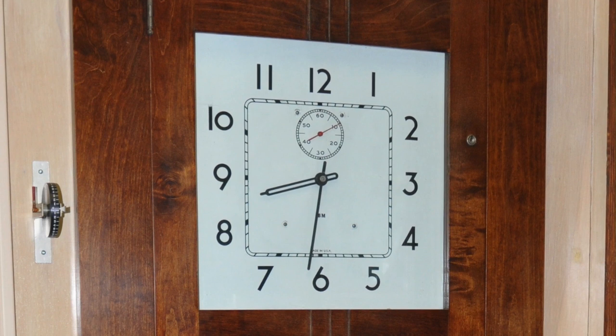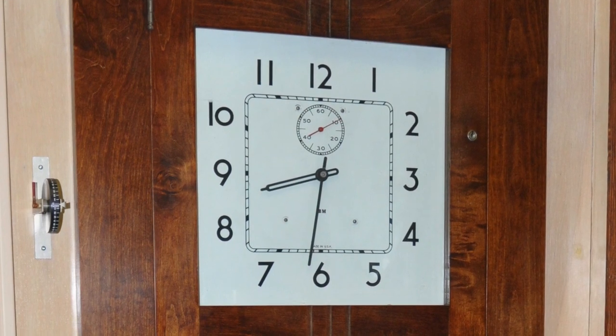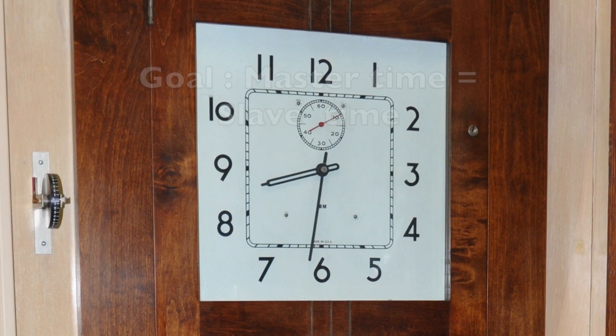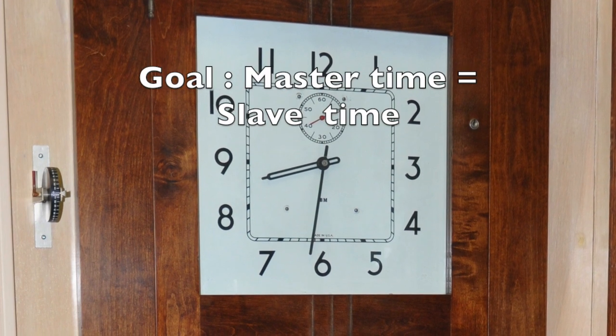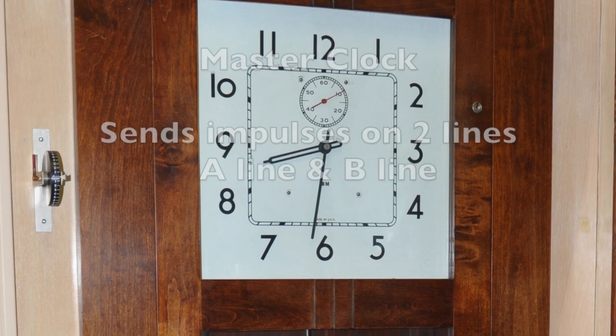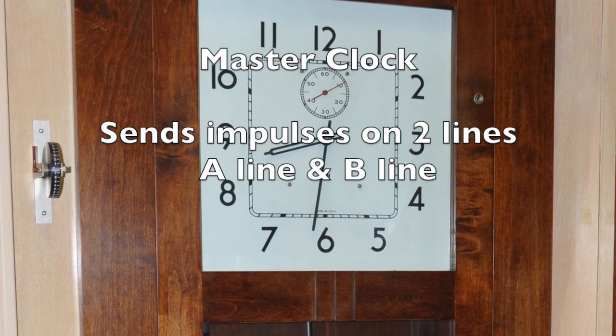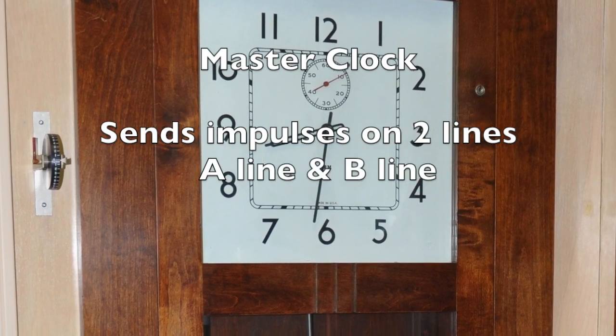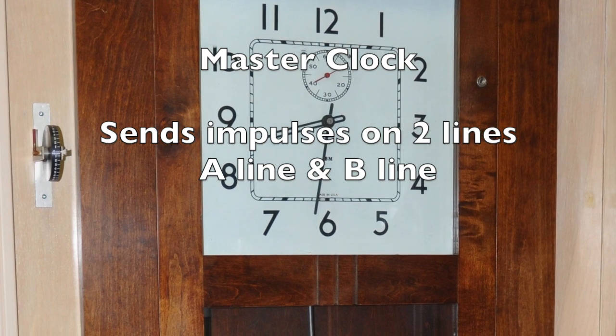Let's start with an overview of the entire IBM master and slave clock correction process. The goal is for the master and the slave to show the exact same time. The master sends minute impulses on two separate lines, the A line or B line.